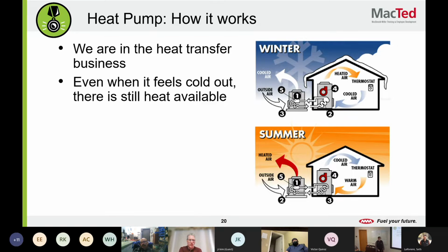So how much more efficient is a heat pump than electric heat? Well, that'll start dropping off the colder it gets outside, but usually it's about 4.5 times, right? It's typically, depends on the COP, depends on the efficiency of the unit you're getting. Then you can go into VRF systems or inverter driven that'll ramp up and down and do all these other things that get way more efficient. But just your basic run of the line heat pump, from my understanding, it's about 4.5 times more efficient, right next to electric heat. Is there anything you wanted to add to that? Nope.